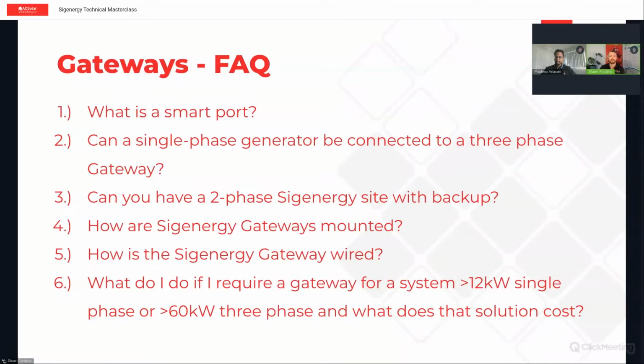Question four: how are Sigenergy gateways mounted? All of the enclosures are a custom Sigenergy IP-rated enclosure, and to keep that IP rating, they have external brackets. You mount the bracket on the wall first, then hang the enclosure onto those brackets. This makes it a lot easier to maintain the IP rating, which is really important since many sites have to go outdoors for space or heat reasons. But it does mean it reduces the ability to do rear entry as nicely - something you sacrifice for that easier-to-manage IP rating.